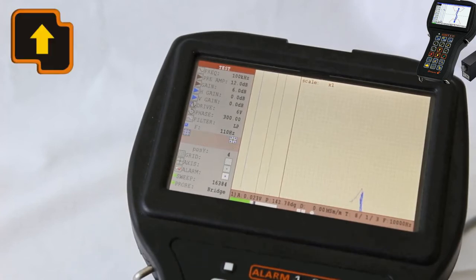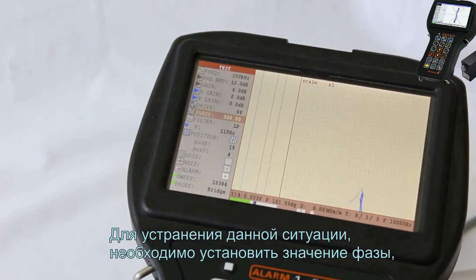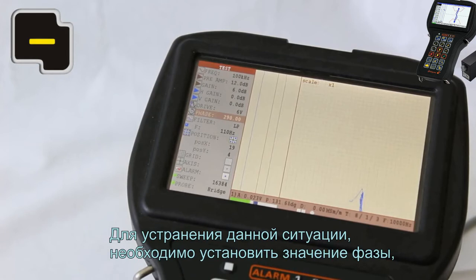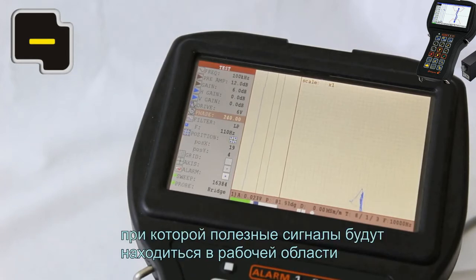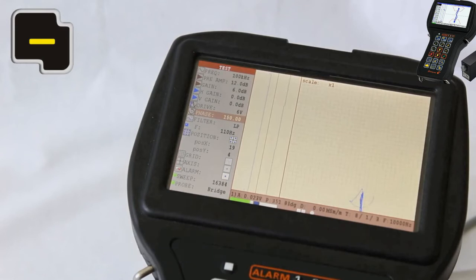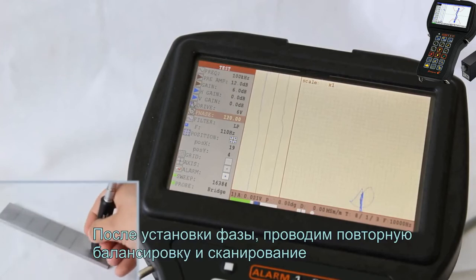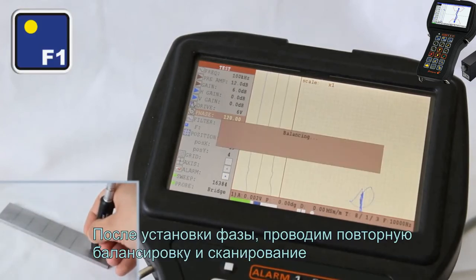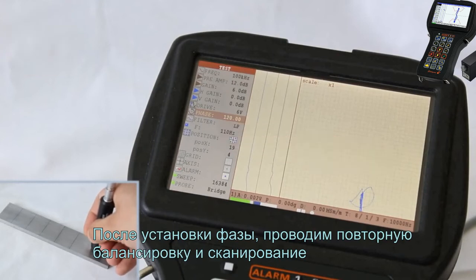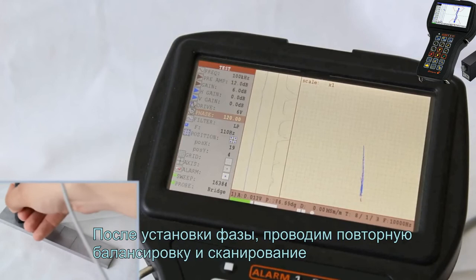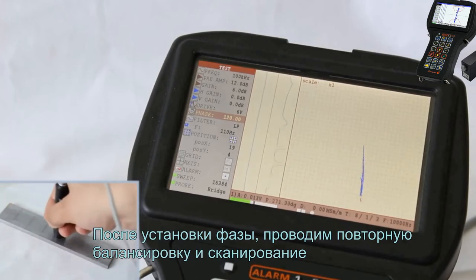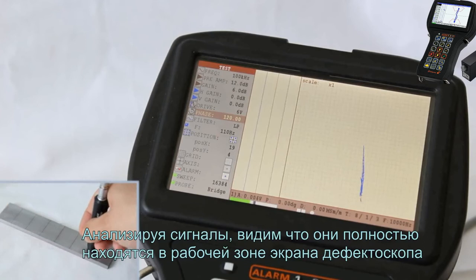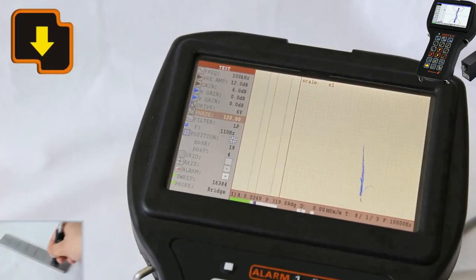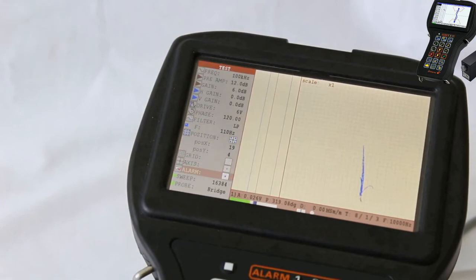We can observe that friendly signals go beyond the active area of a screen. To eliminate this, you should set up the phase value at which the friendly signals will be located in an active area of a screen. After the phase was set up, perform the repeated balancing and scanning. When analyzing the signals, we can observe that they are fully located in an active area of a flaw detector screen.